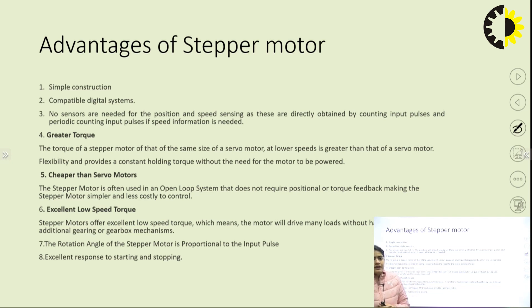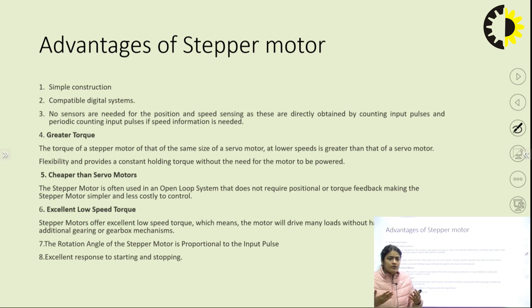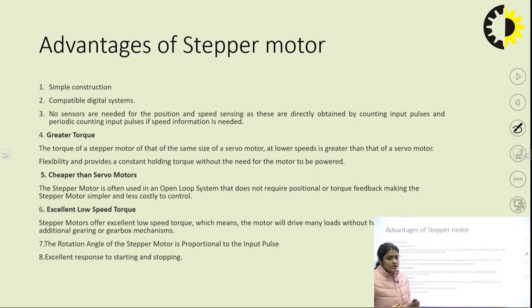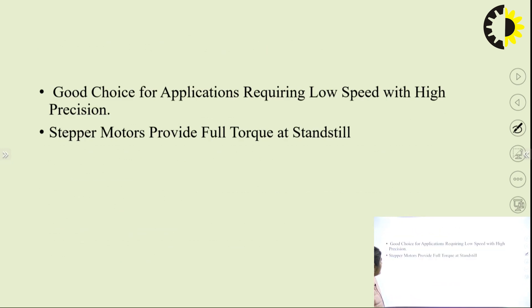That is why the stepper motor is preferred for precise position control — it has simple construction, provides higher torque at low speed, requires no sensor, and can be used in open loop with no complex controller needed. The cost is also reduced, and since the rotor has no winding, winding cost and maintenance cost are both reduced, lowering the overall cost. These are the features and advantages; in terms of application choice, it is preferred where low speed with high precise torque is required.